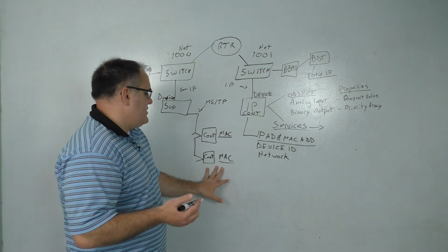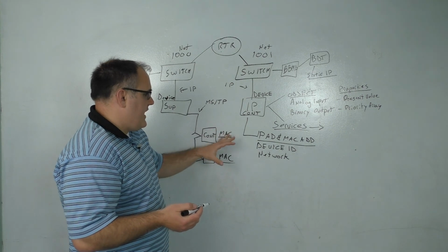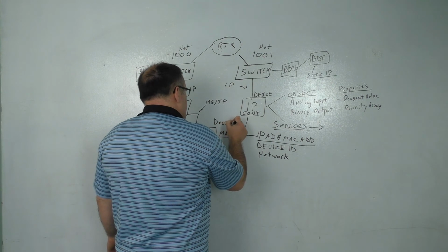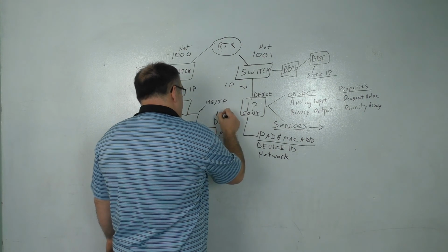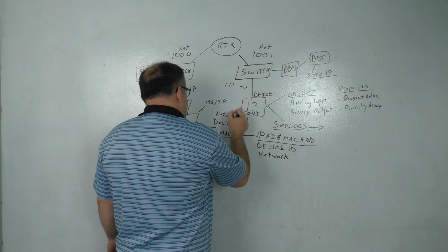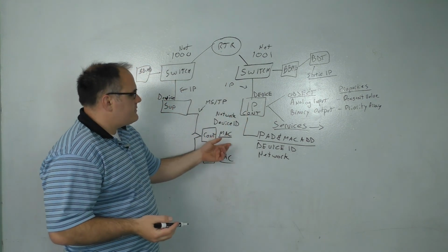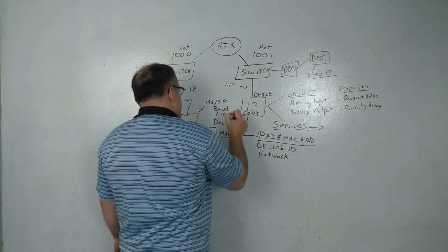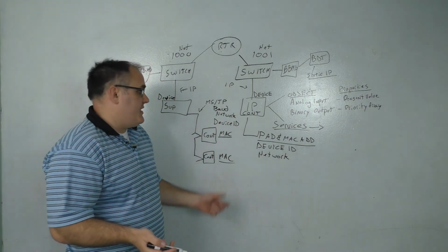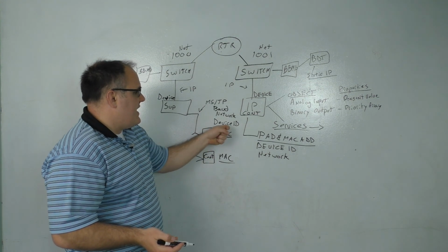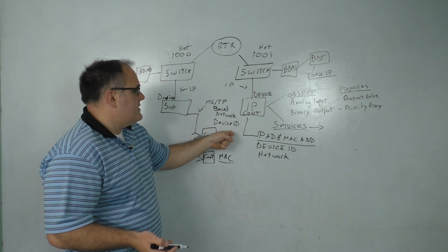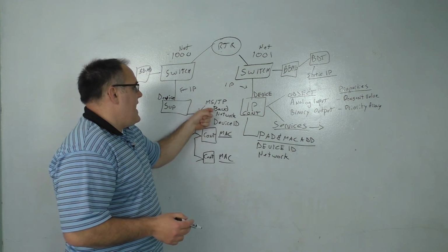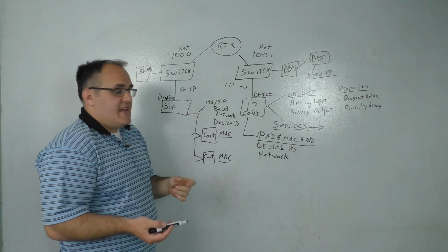And that allows you to set a physical address on the controller. You still have your device ID. You still have a network number, albeit it's for the MSTP network. And you now have a baud rate, which is the speed. And this is where a lot of issues happen. A lot of issues with BACnet MSTP networks come from duplicate MAC addresses, duplicate device IDs. That's across BACnet that causes issues. And baud rates that aren't the same, speeds that aren't the same.